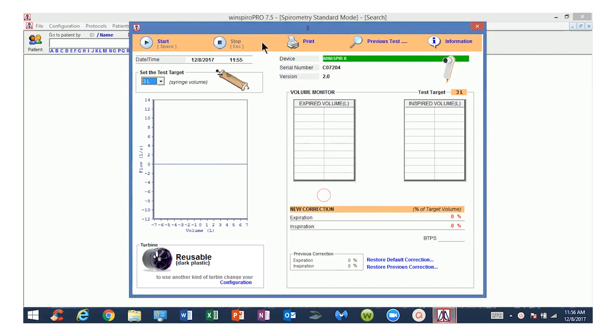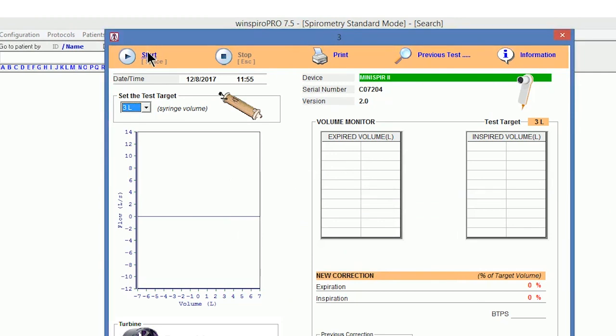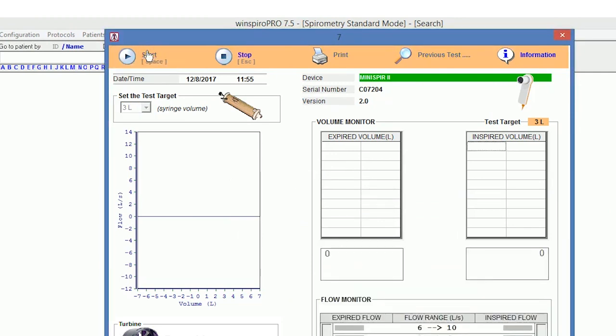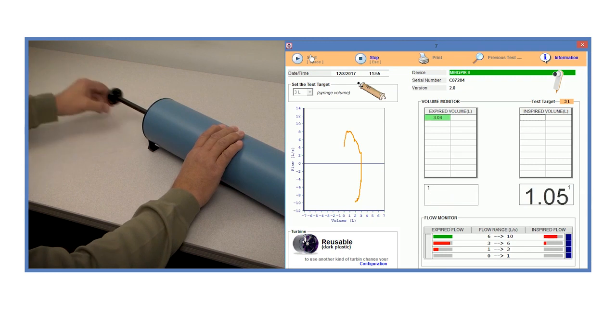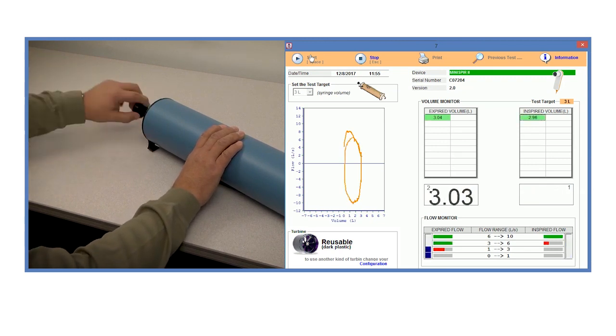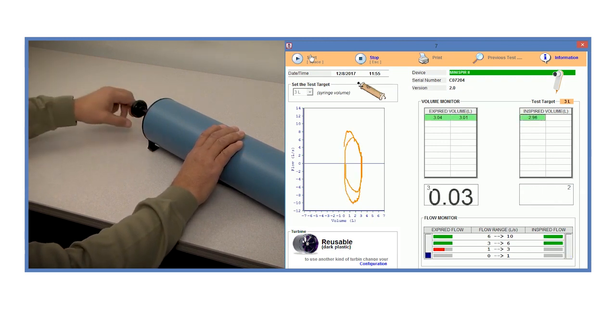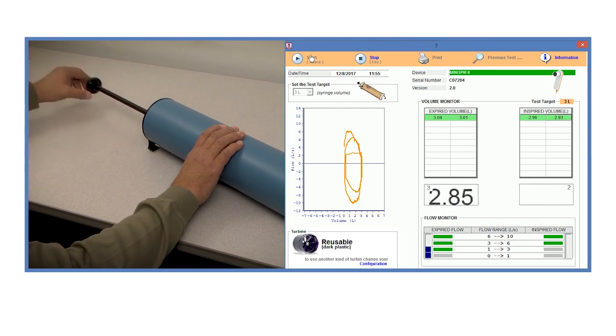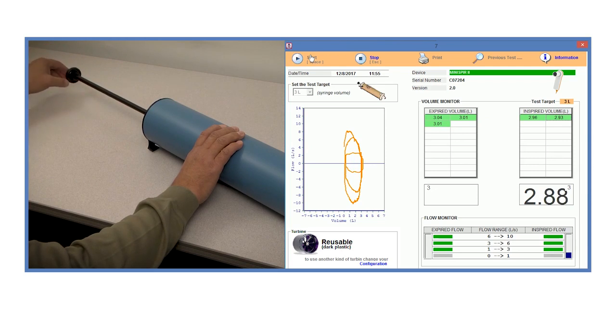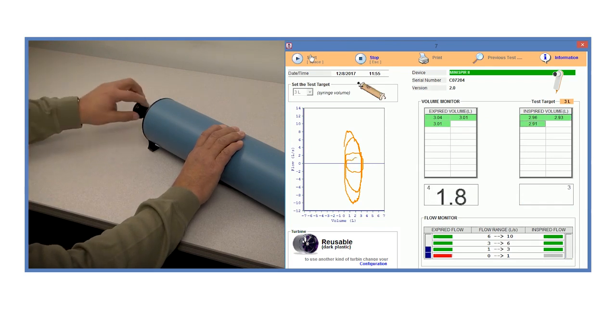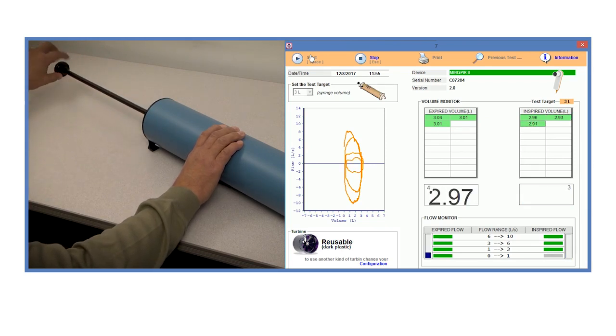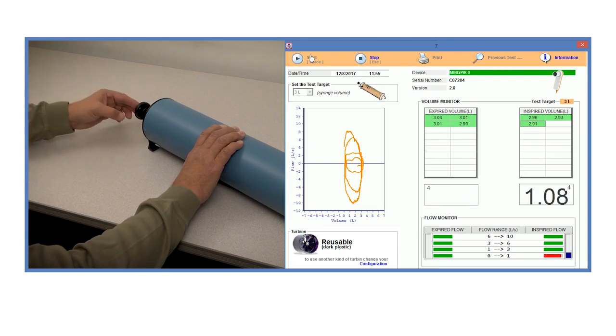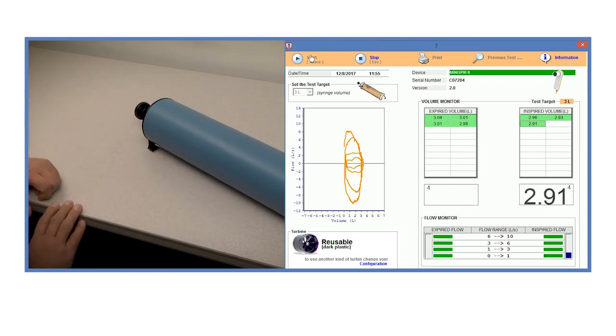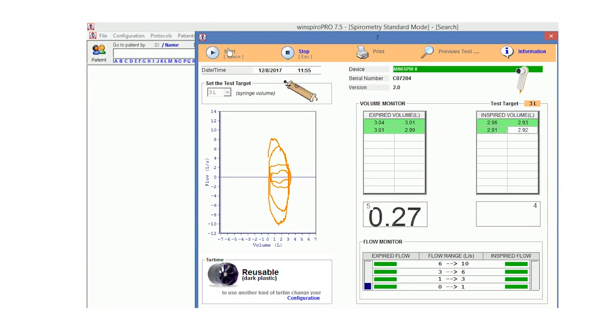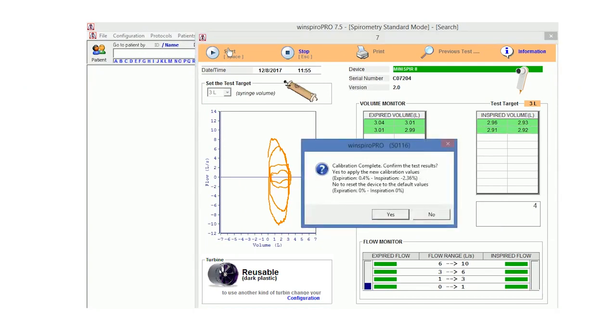You may begin the test by pressing the spacebar on the computer or clicking the Start icon at the top of the screen. Begin to push the syringe piston in and out smoothly at 3 different speeds: fast, medium, and slow, until all the bars under the expired flow and inspired flow are green. Be sure to pull and push the syringe piston all the way to the built-in stops in each direction. When all bars are green, the test will stop automatically.